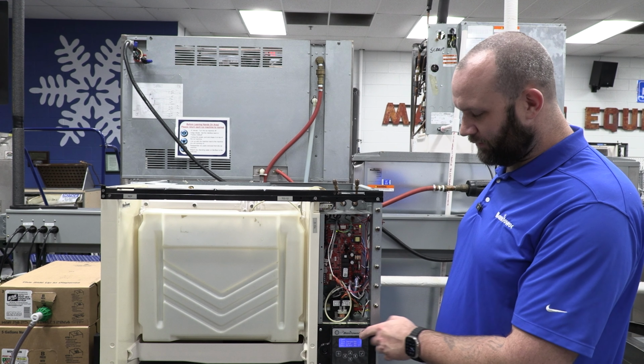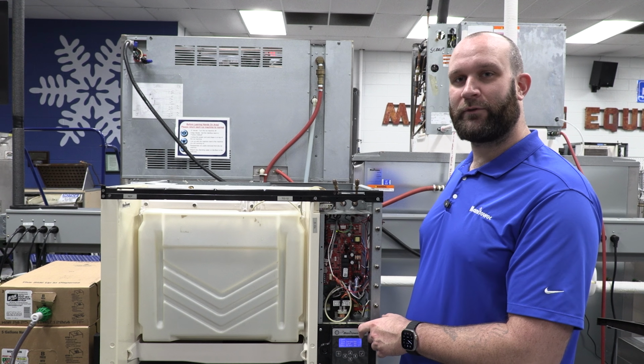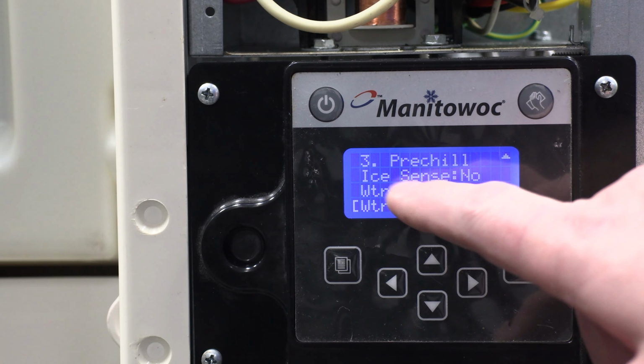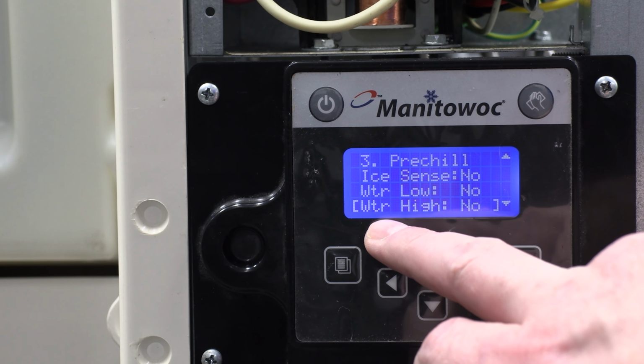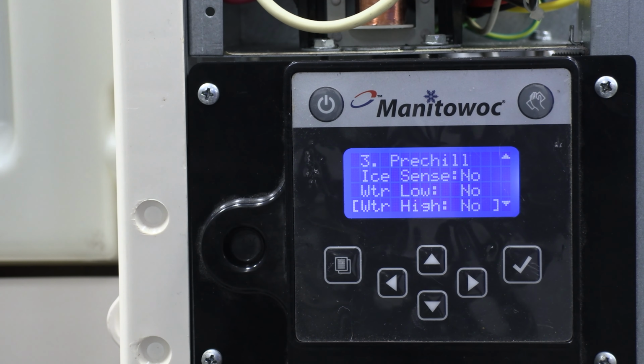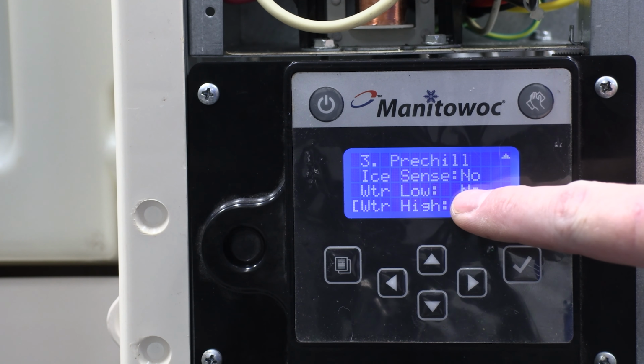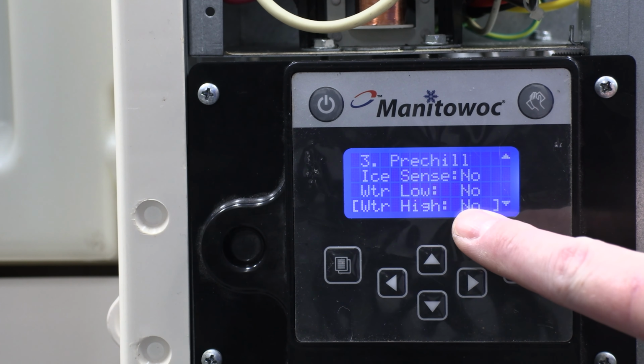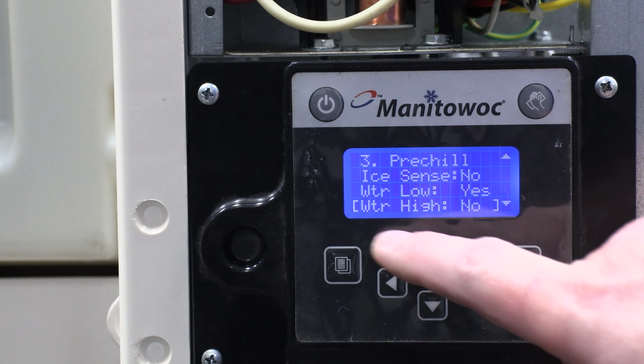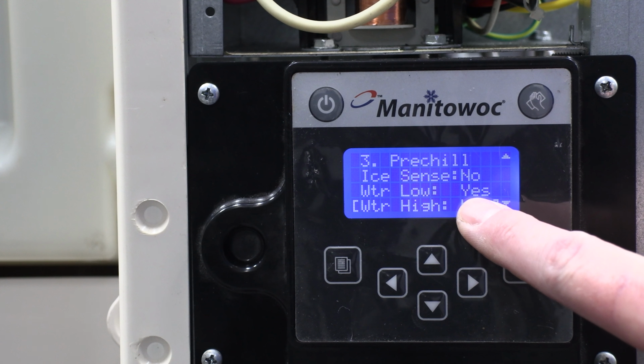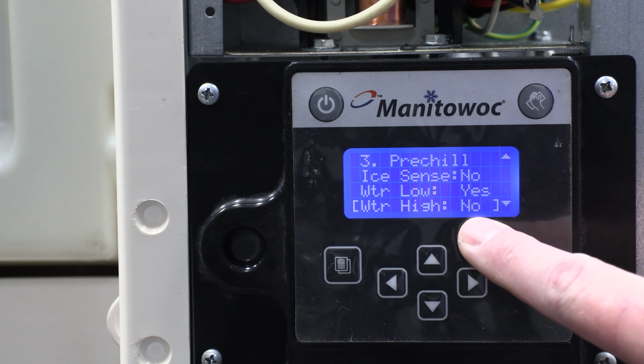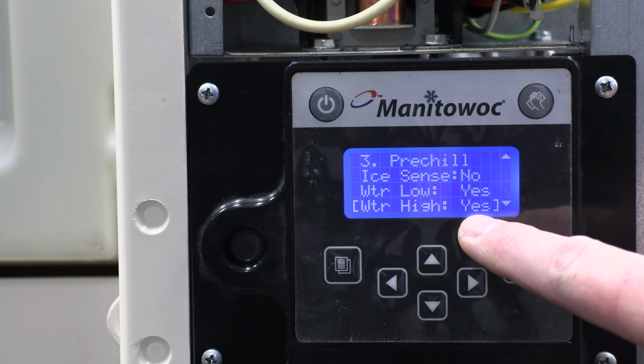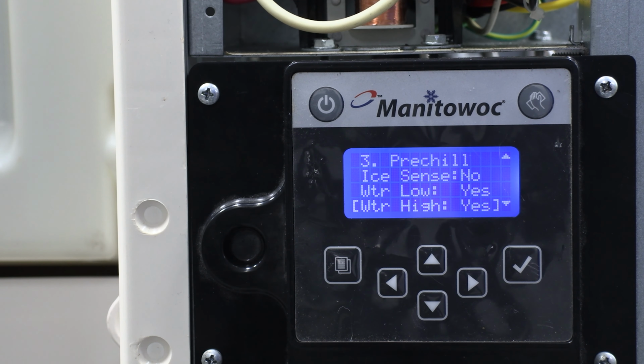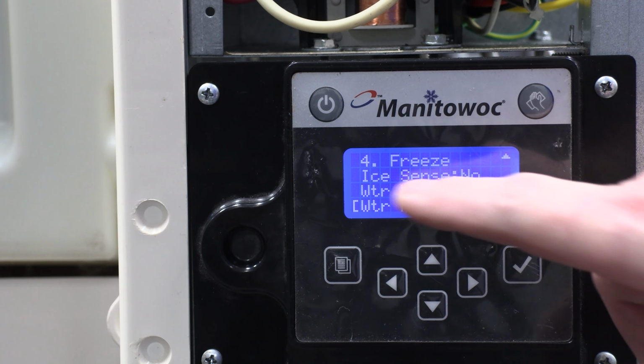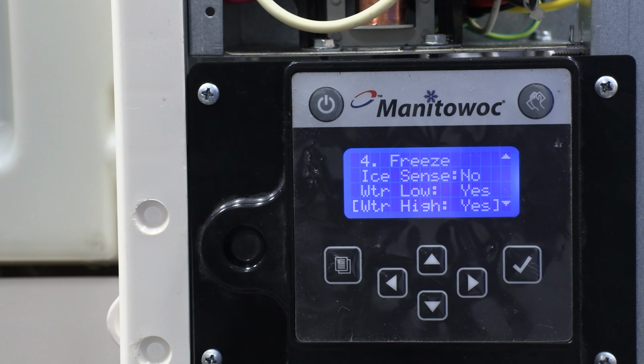So now that I've replaced that, I'm going to power on the machine and monitor its operations for a few batches of ice. So as you can see, our machine just went into pre-chill. We're going to monitor the water low and the water high level and make sure that they're reading properly. You should always receive water low yes, and then water high yes. Okay, so you see we just reached our low water level probe. So we are saying yes there. The machine is going to keep filling until it reaches water high. It just reached water high. We've stopped filling. Okay, so now that our water level probe is reading properly, we have gone into a freeze mode and did not skip right into harvest.